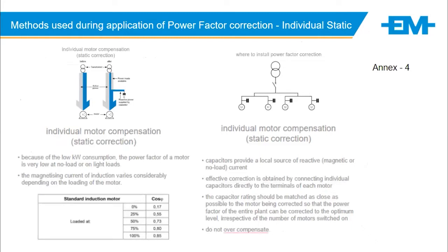The other way, which is quite an old way, which people do, I don't like it, because you're going to land up having more equipment spread out all over your site, is individual motor compensation. So at your physical motor, the customer would put down a capacitor bank with a contactor. As the motor starts up, if it was on a star delta, when it switches over from star to delta, it would bring in the capacitor. All right, and it would only be compensating at the motor itself. The issue with this is, if anything goes wrong, you can overexcite the motor if a cap stays in, even though the motor is off, and you've got a lot of disparate equipment all over your site at each motor. Personally, do it upstream. Okay.